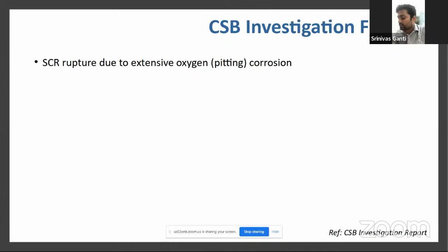The first thing they observed was that the SCR was ruptured due to extensive oxygen in the makeup water, causing pitting corrosion. As we all know, enhanced dissolved oxygen in the water, combined with high temperature and pressure, will enhance corrosion. That pitting corrosion due to dissolved oxygen was the primary reason they identified.